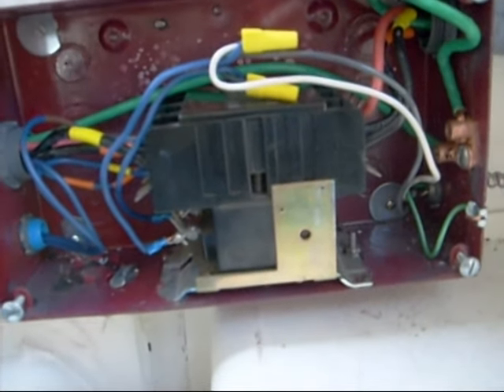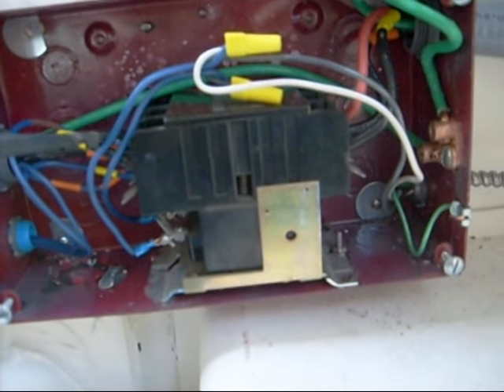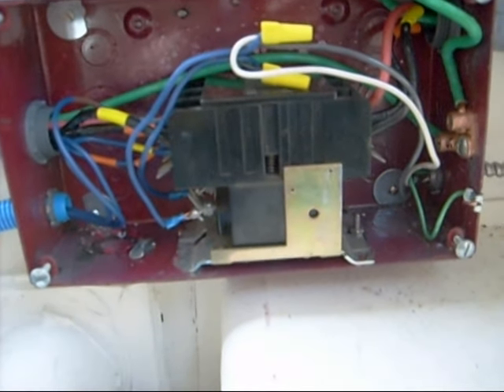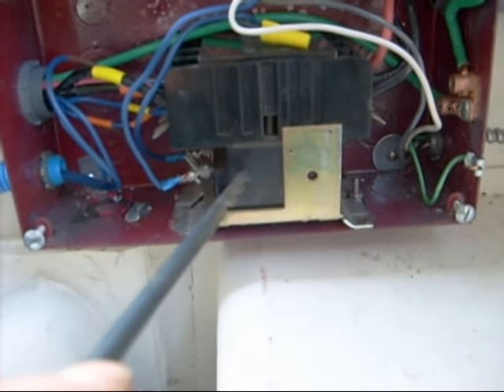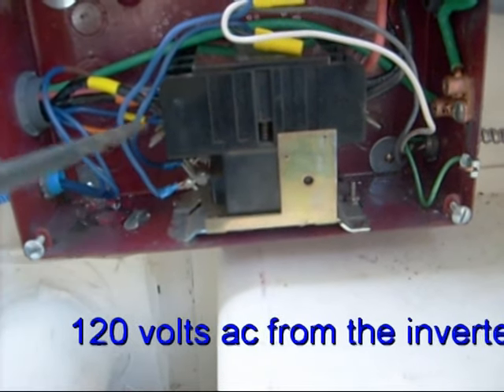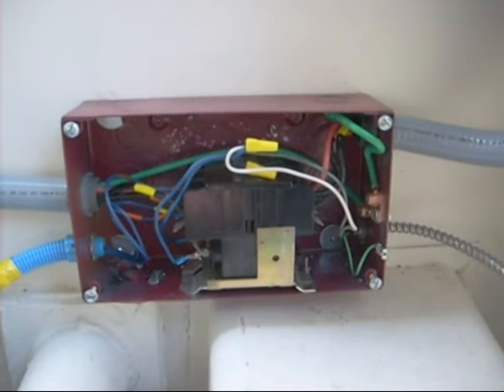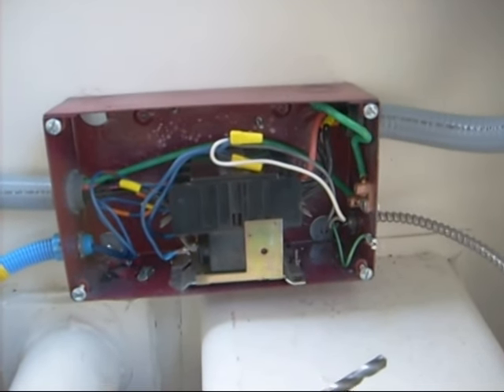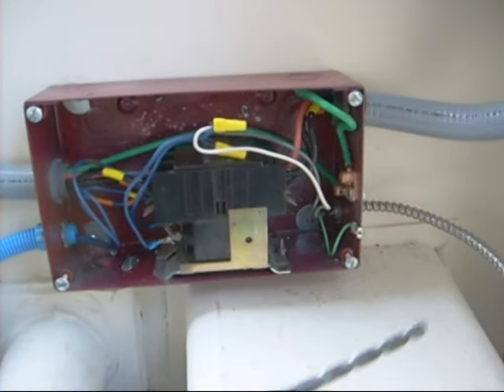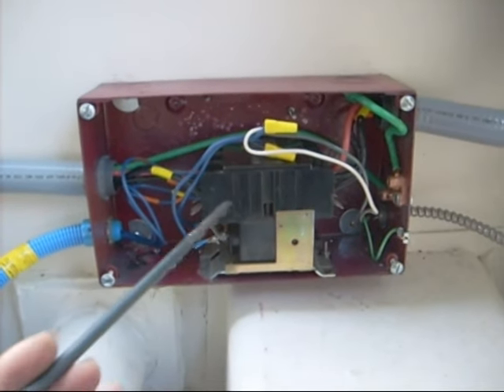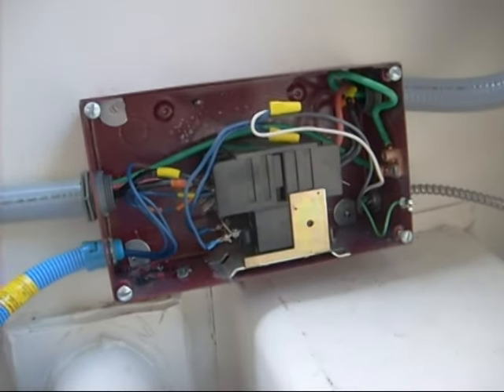On this side of the contactor we have the three wires coming from the alternator. On the other side we have three wires going from the contactor to the disconnect. When I put 120 volts into this coil, it will close the contactor and allow electricity to flow into the disconnect. I'm thinking you want to get this thing up to voltage before kicking in the contactor, so we're going to make sure we've got full voltage happening before I close the contact.